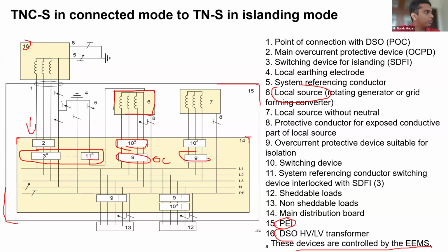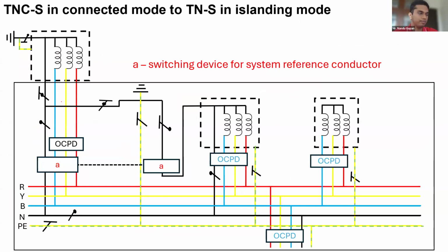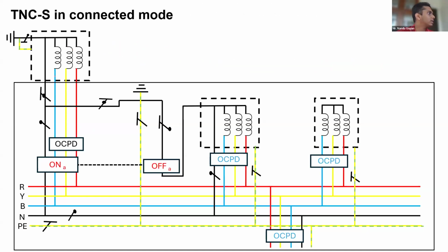Now I'll simplify this diagram. I'll take these overcurrent protective devices out and make a much simpler diagram. So this is how it looks, a little more simplified. This is from the discom. This is source 1 and this is source 2 inside the PEI. This is the PEI. And this should actually be in the main distribution board. From the discom, it is TN-C-S in connected mode, meaning a TN-C-S conductor is coming from the discom. There are four live conductors. System referencing has been done here. The neutral and PE have been connected here, and from the installation, four conductors will be coming inside.